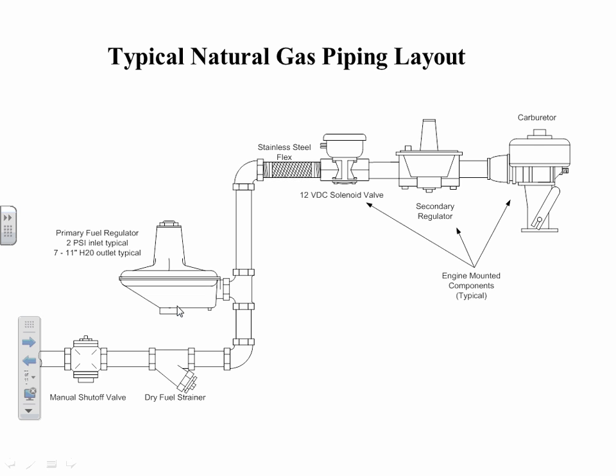Typically, most like a residence or something, and small business, is going to have like a 2 psi inlet. Maybe Dunwoody would have the same size here if they're running furnaces or something. 2 psi is very common. And the outlet pressure is between 7 and 11 inches of water. Okay, anything that's connected to the engine has a chunk of flex in it someplace because the engine rocks. So that gives it a little bit of flexibility there, so it can rock and start up and so on.